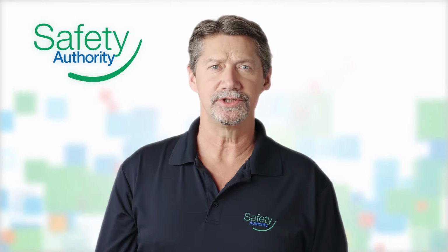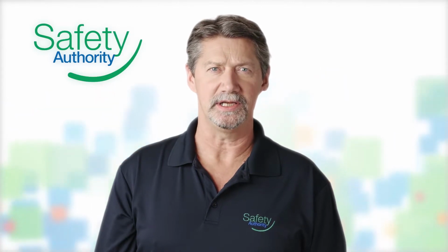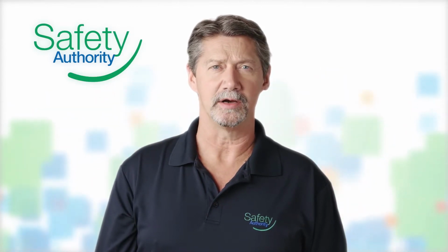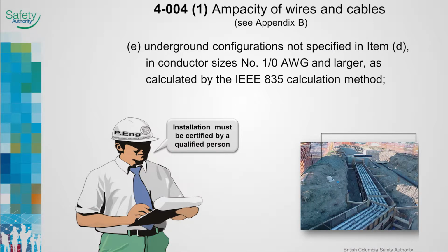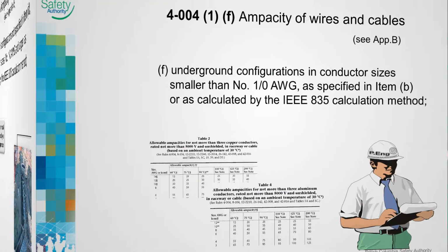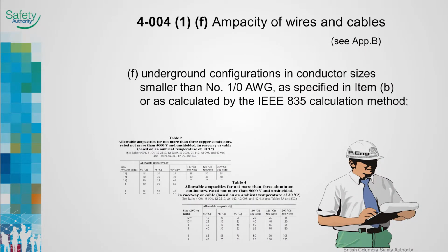If the underground installation is not in compliance with Appendix B, then a professional engineer will be required to perform the calculations. Depth, spacing, ambient temperature, loading, and other factors all affect the allowable ampacity of underground conductors. Rule 4-004-1F permits the ampacity of a conductor smaller than 1/0 and run underground to be selected using either Table 2 for copper or Table 4 for aluminum. Alternatively, the IEEE 835 calculation method can be used.